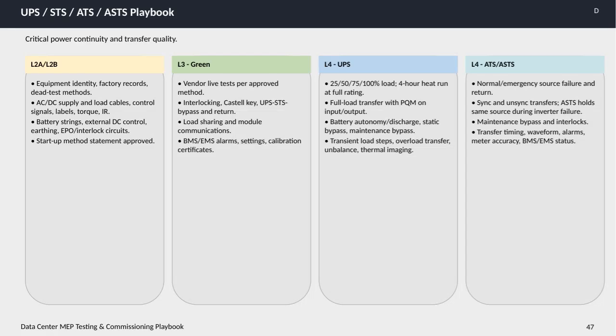This slide outlines a UPS, STS, ATS, and ASTS playbook focused on critical power continuity and transfer quality within data center MEP testing and commissioning. Starting with level 2A and 2B checks, we verify equipment identity against factory records and conduct dead test methods. We inspect AC and DC supply and load cables, control signals, labeling, torque settings, and insulation resistance. Battery strings and external DC controls are reviewed, along with earthing systems and emergency power-off or interlock circuits. It's essential that the startup method statement is fully approved before proceeding.